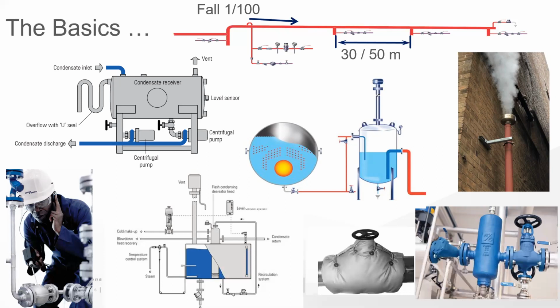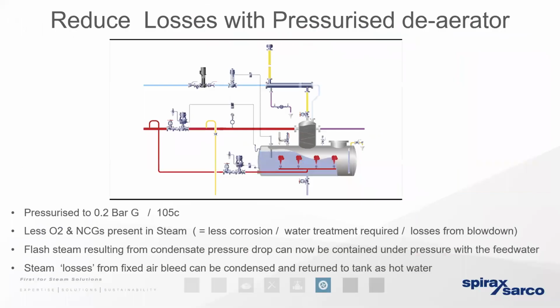Now, there's one such solution that we have spoken about previously. We've spoken about a traditional atmospheric hot well before. That's where we know that we can only contain the feed water at atmospheric pressure, zero bar gauge, meaning we can only hold the water at 85 degrees. So that means that quite a lot of the flash steam will still be lost in the boiler house itself to protect those pumps from cavitation. So if we've got a loss of flash steam, we're going to experience a significant loss of not only energy, but we're reducing the amount of condensate that is going to be returned to the feed tank itself.